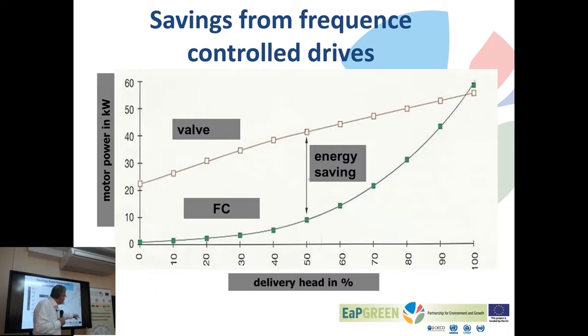So if I reduce water flow from 100% to 50%, the power of the motor in throttling conditions comes down from 60 to 45. Whereas if I use a frequency controlled drive in the same situation, reducing delivery head from 100 to 50%, the power of the motor would come down to 10 kilowatts. So using frequency controlled drive would reduce power consumption for the same condition to a little bit more than 20% as compared to controlled by a valve.